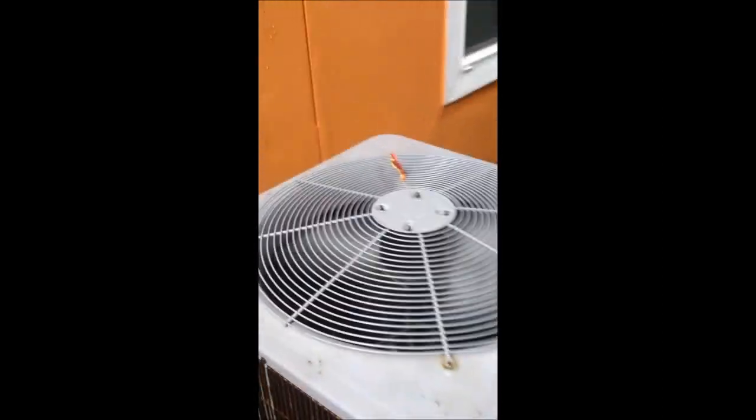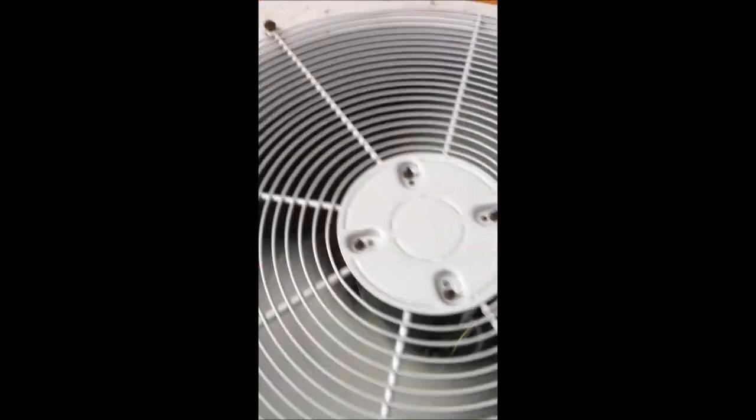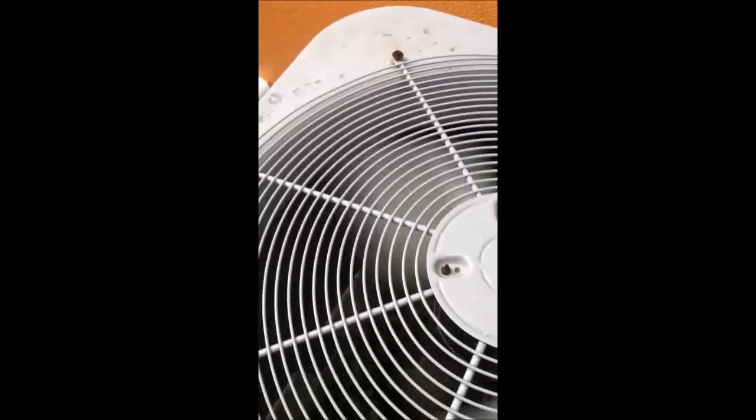And the reason that it sounds so terrible is that there are condensation drain plugs on the bottom of these motors.